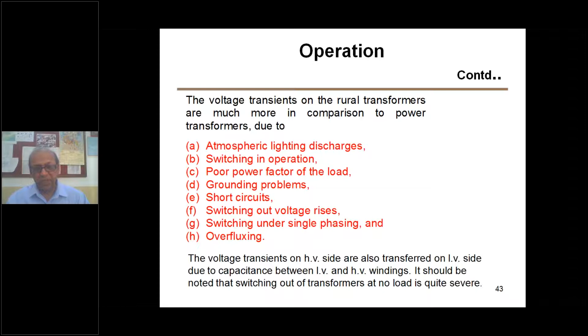Switching out is also a problem issue — you should not switch off the transformer at no load. Switching off the transformer at no load causes a surge of high voltage within the winding, which may cause failure. Remember again: transformers should not be switched off at no load; you must have some load. That way, whatever energy is in the inductance of the transformer is dissipated when switching off. Otherwise, it will not be dissipated, and there will be high voltage, which may unnecessarily cause the failure of the transformer.